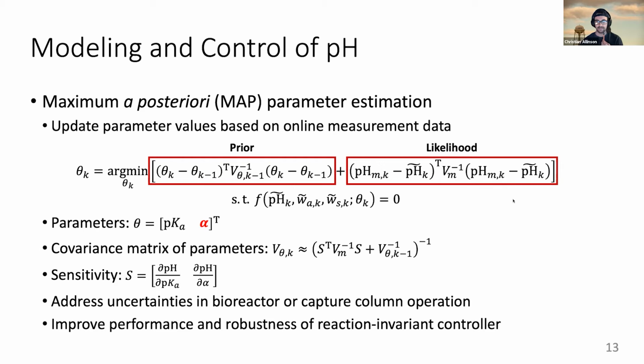Yeah, the plant I worked in, we did pH balancing and we had a strapping table. So given a current pH, we kind of knew how much dose we needed to get into the range we wanted, and then used a PID controller to fine tune it. But I think tons of people have their own opinions on the best way to do pH control in practice.